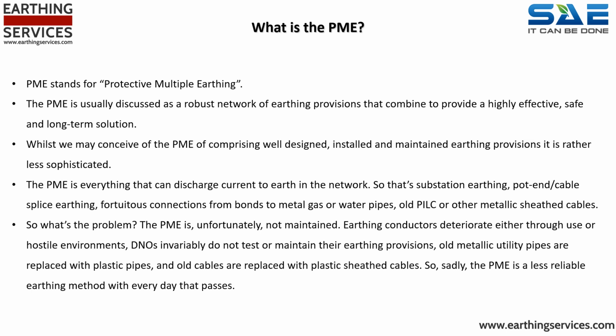So that's substation earthing, pot end, cable splice earthing, fortuitous connections from bonds to metal gas or water pipes, old PILC, or other metallic sheath cables. So what's the problem? The PME is unfortunately not maintained. Earthing conductors deteriorate either through use or hostile environments. DNOs invariably do not test or maintain their earthing provisions. Old metallic utility pipes are being replaced with plastic pipes, and old cables are replaced with plastic sheath cables. So sadly, the PME is a less reliable earthing method with every day that passes.